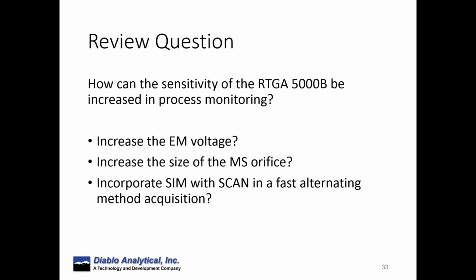So this is the mode that we normally recommend that we start out with first. Let's think here a little more closely. How can the sensitivity of the RTGA be increased in process monitoring? Well, one idea is we could increase the EM voltage. That's the electron multiplier, the ion detection. That's like turning up the gain. Now, the downside is that if you just turn up the gain, you're going to increase the signal, but you're also going to increase the noise. So typically, you don't win with that. You don't get any additional signal to noise by increasing the EM voltage.